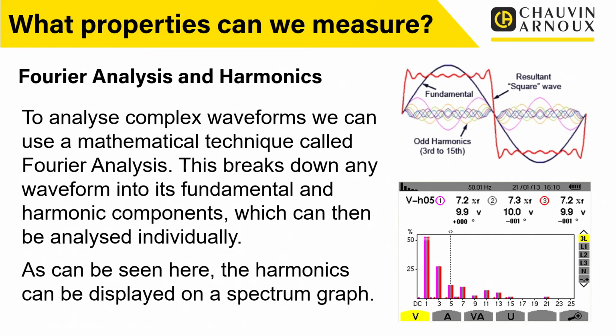We use Fourier Analysis, and Fourier Analysis then allows us to plot, as you can see there, the spectrum of these harmonics on a graph. So what we can see is that the distortion is made up of the fundamental frequency, but also it's made up of these various harmonic components. And by looking at these harmonic components, quite often we can use that to diagnose what might be causing it. Because through experience, we know that if there's a lot of a specific harmonic in there, that is likely to be caused by a particular type of circuit or a particular type of load. So then we can go looking at that and say, actually, yeah, that's where the problem is. That's what's been causing it.